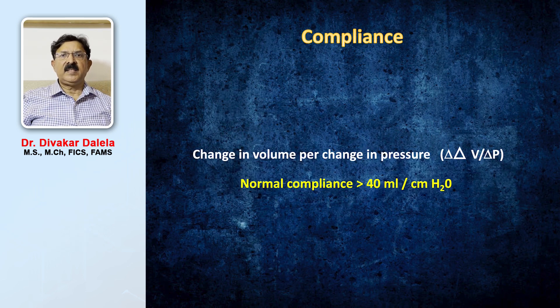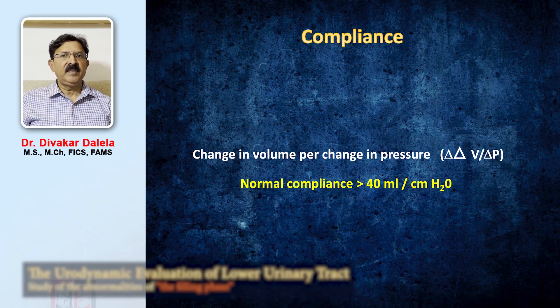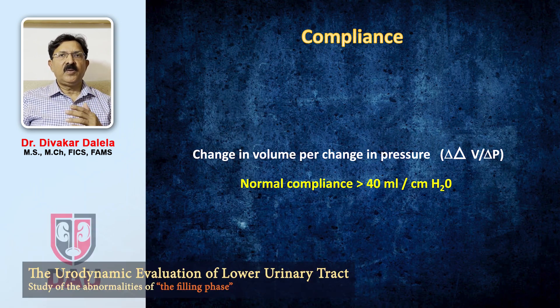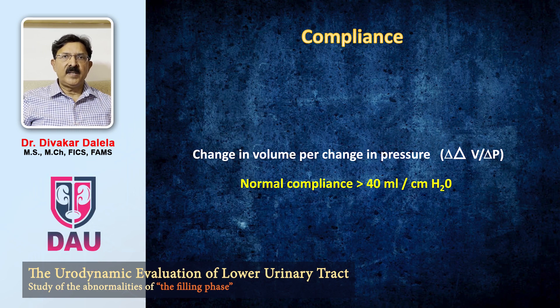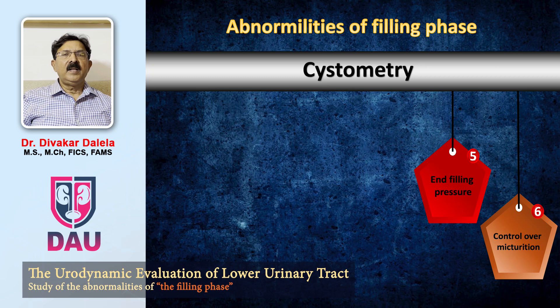The compliance, as I said, you can suspect poor compliance by just observing the consistent elevation in the pressure line. But you can also calculate this by change in the bladder volume divided by change in the pressure. The normal compliance should be 40 ml per centimeter of water.